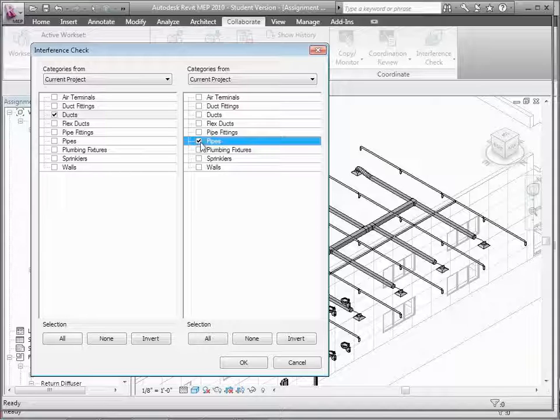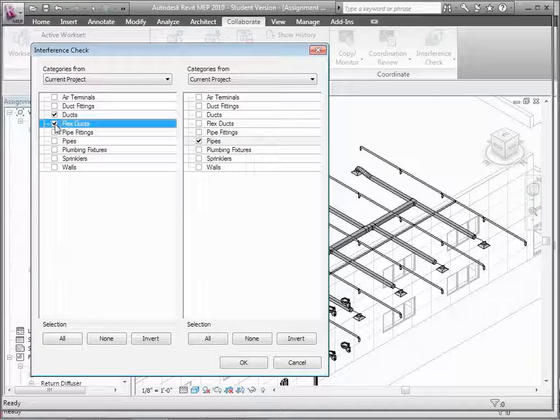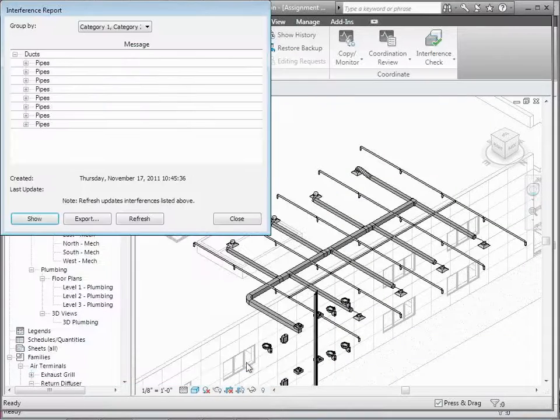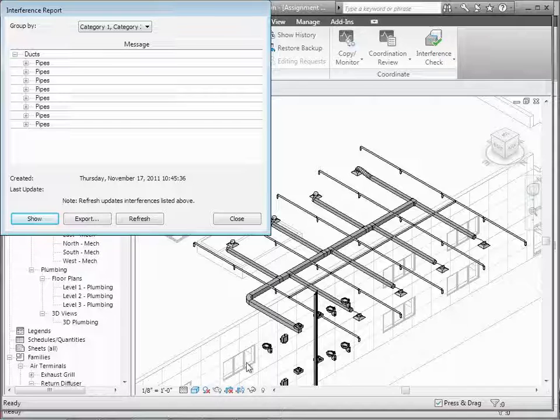I'm going to compare things in category A to category B. If I chose ducts versus ducts, I'd be looking for ducts overlapping each other in a way that's not a valid connection. But let me look at ducts and flexi ducts versus pipes. When I click OK, we actually have some problems here. We can see that for some ducts there are interference problems with some pipes. Each of these different items is considered an issue that needs to be resolved.